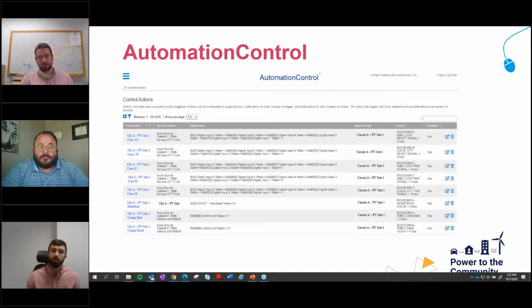So what we did is we monitor the TH66 micro RTU for those 6 inputs, and we wrote if-then statements that look at those 6 inputs and then initiate a sequence of outputs based on what it receives. So if breaker A trips, then we know we need to trip sites 1, 2, and 3. Each one of those is written in here, and it all works simultaneously. When the conditions are met, each one of them fires and trips off the PV sites, and then we wait for that reset to bring them back online.